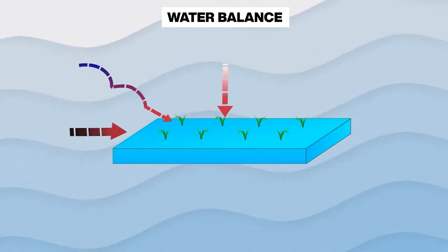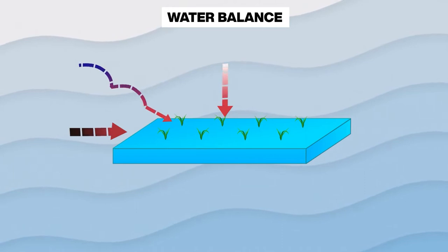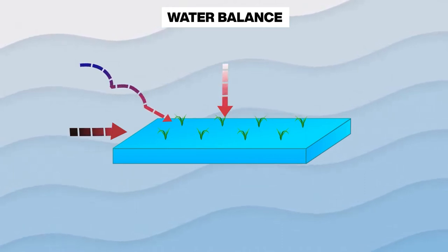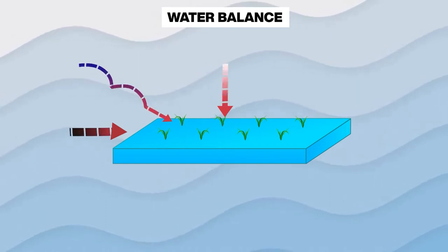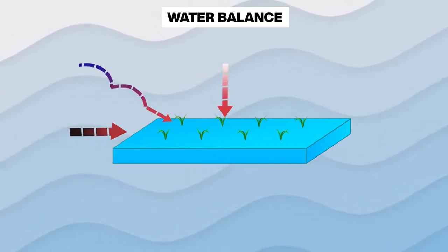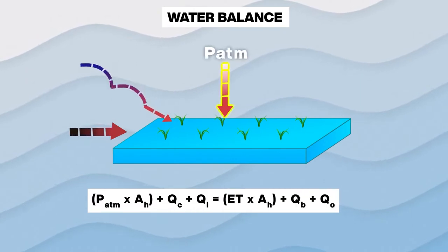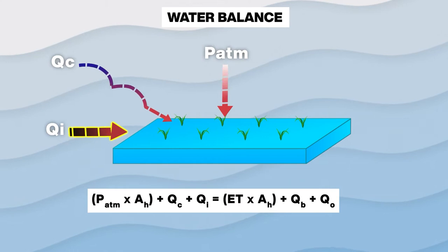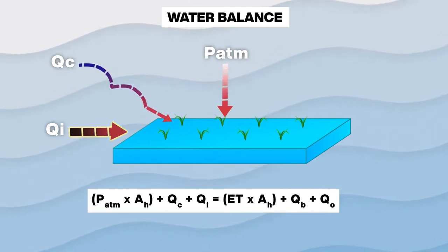Moreover, we should definitely take into account that any type of constructed wetland is part of the landscape. Any landscape incorporates atmospheric precipitation and storm runoff. In addition, constructed wetlands are a part of the landscape and, as a treatment facility, also have to incorporate wastewater that's to be treated. Because of this, a wetland's hydraulic load consists of 3 components: atmospheric precipitation, storm runoff, and wastewaters that transport biowaste generated by humans.